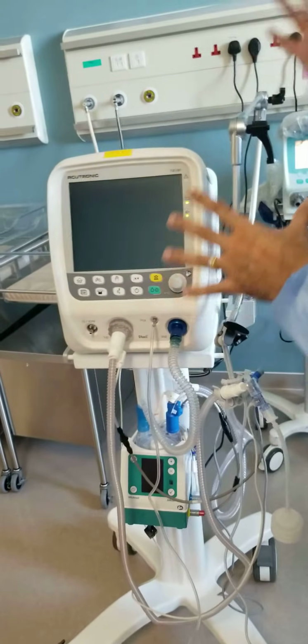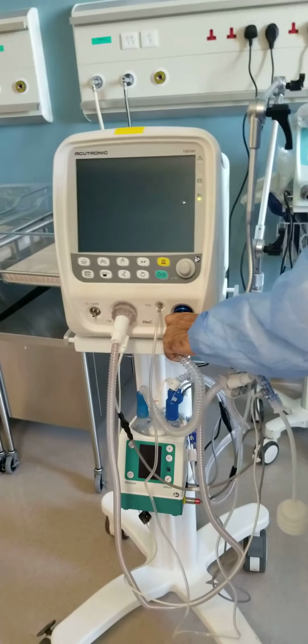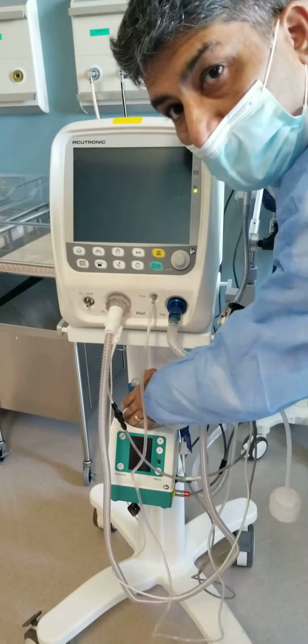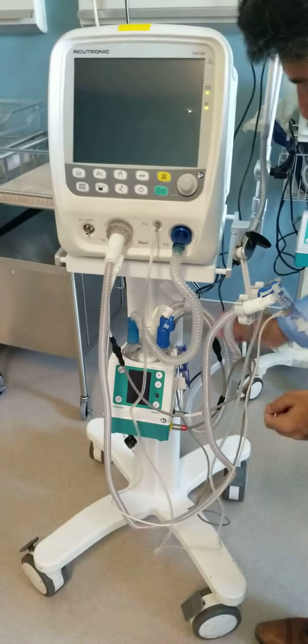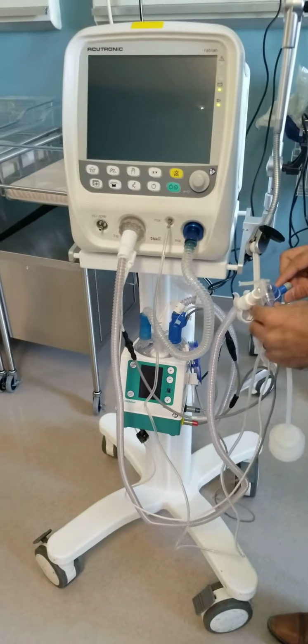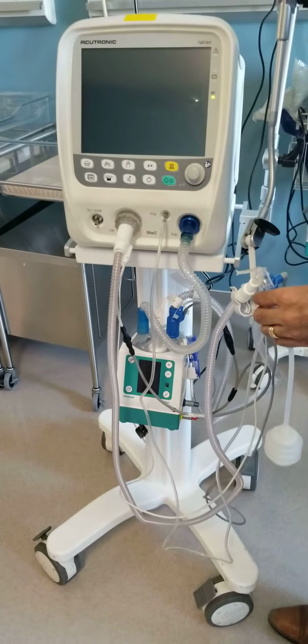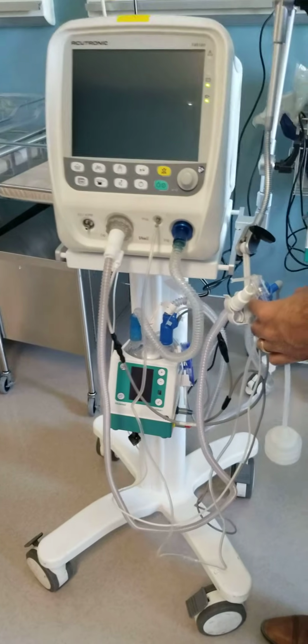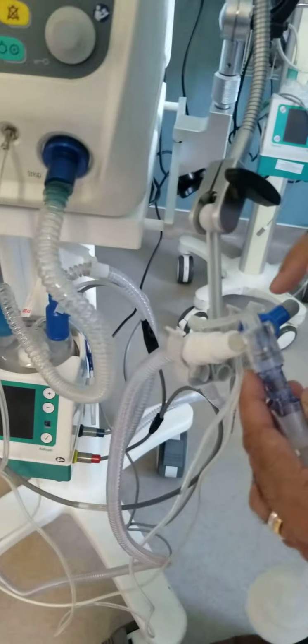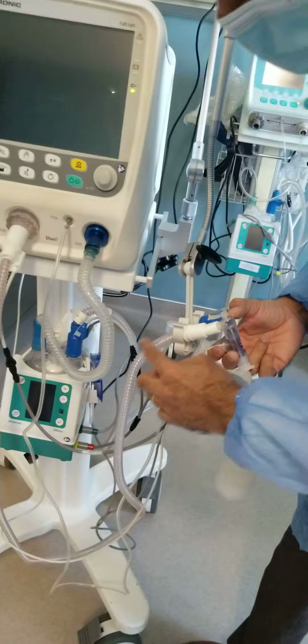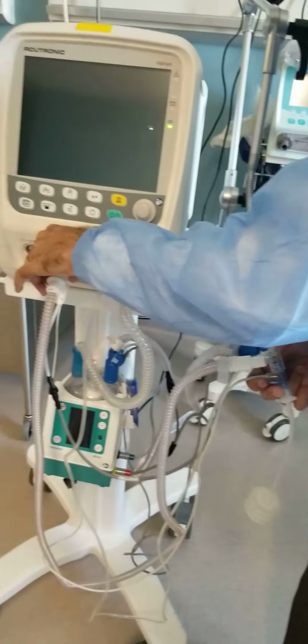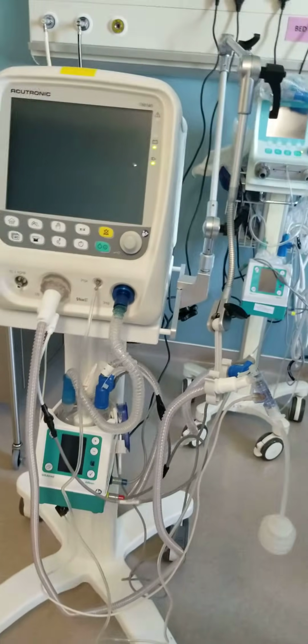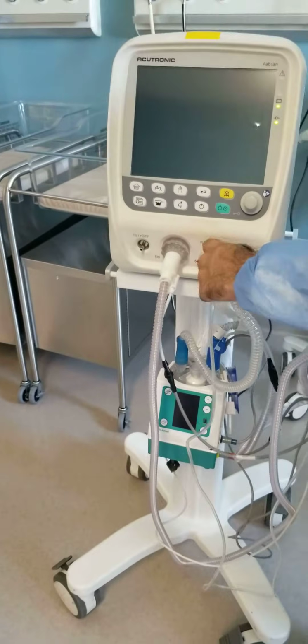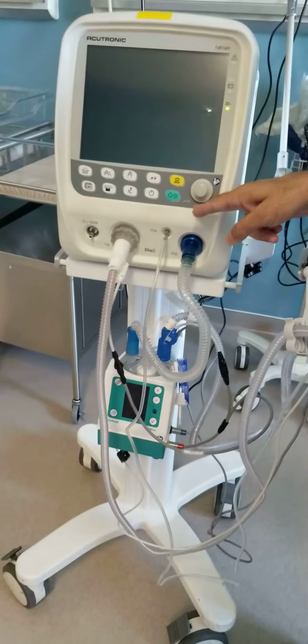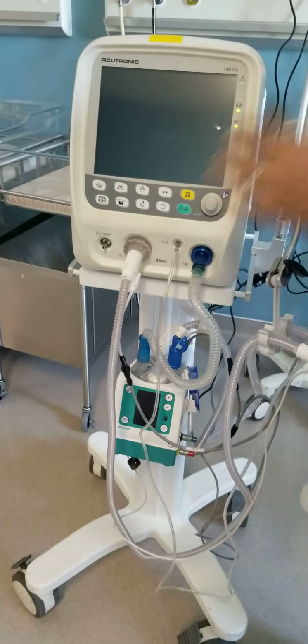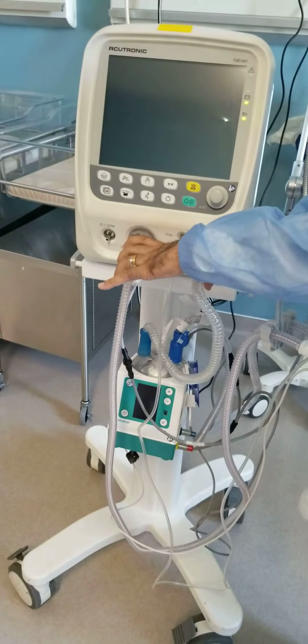In front, as I said, like any ventilator, you have the inspiratory side. The fresh gas goes to the humidifier. Humidified air goes to the baby. You have a flow sensor here to measure the tidal volumes of the babies and also to pick up the trigger for synchronization. Then you have the expiratory limb coming out here. And then you have your pressure being monitored, so that's why you have the pressure line. So these 3 will be your conventional modes of ventilation.